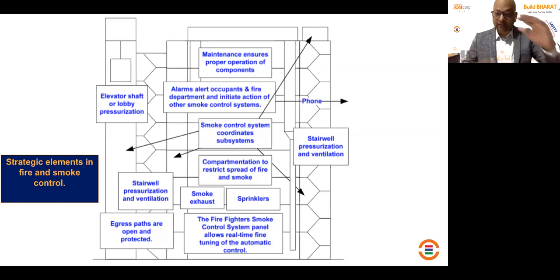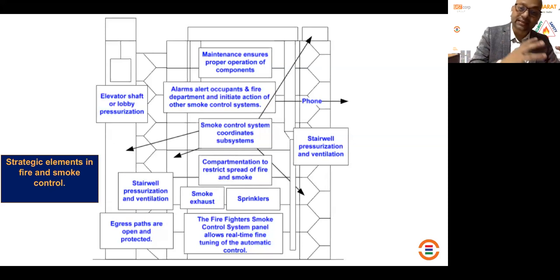The same goes for your lift. Depending on the height and adjoining area, you can also pressurize the hoistway, the elevator shaft. That has to be injected at 50 Pascal, with a difference of 25 to 30 Pascals. So you maintain that pressure in the lift well so smoke will not get inside it.